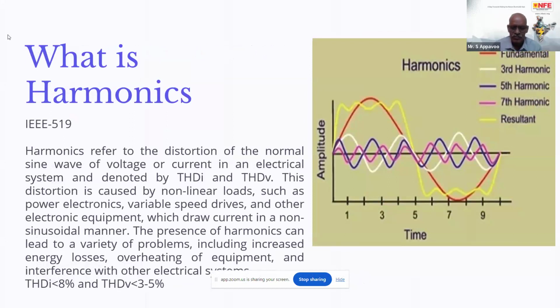So basically, when our fundamental waveform, which is of 50 hertz, because in India we work on 50 hertz, gets distorted and converted into integer multiples of the fundamental frequency, it can be 150 hertz, that is the third harmonic, or 250 hertz, that is the fifth harmonic, or the seventh harmonic, or the 11th harmonic. It could be any one, depending upon the integer value of that harmonic.